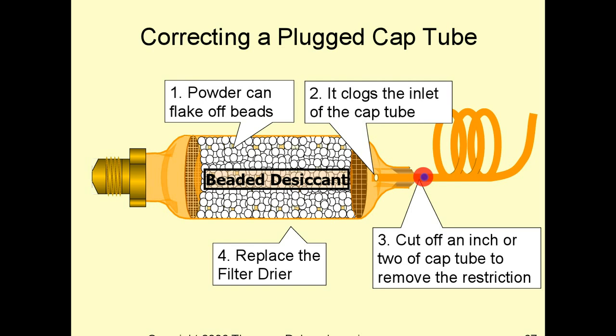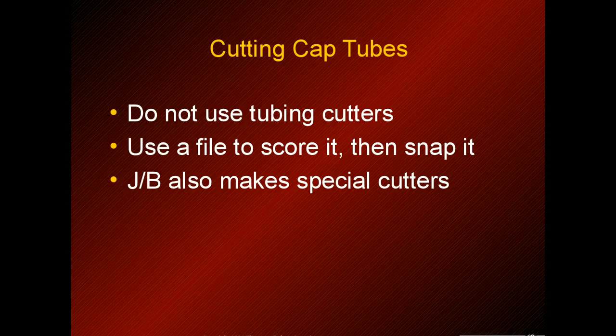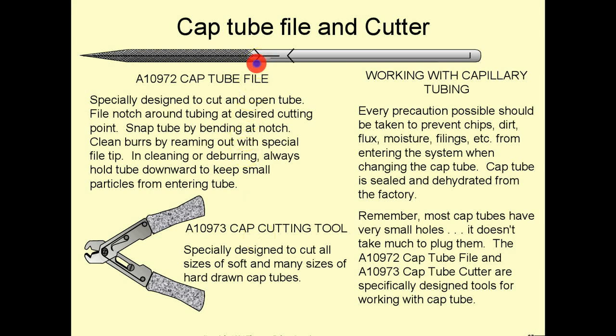When brazing the cap tube back in, make sure you push enough of the tube in so that brazing doesn't plug the small end, but not so far that it's smashed against the screen holding the desiccant. When cutting a cap tube, don't use tubing cutters — they compress the inside diameter and cause issues with pressure drops. Instead, score the cap tube with a file or a cap tube cutting tool, then snap it off by holding it between your thumbs and fingers with both hands.